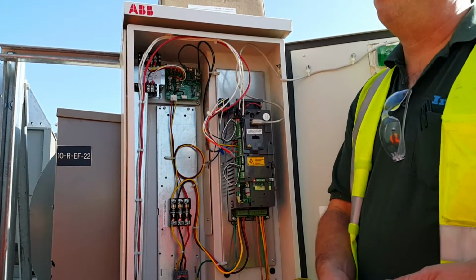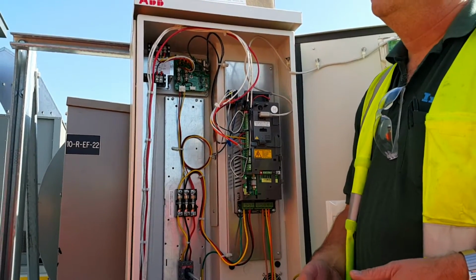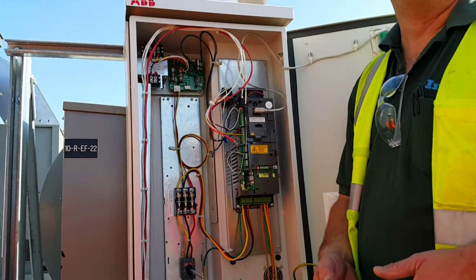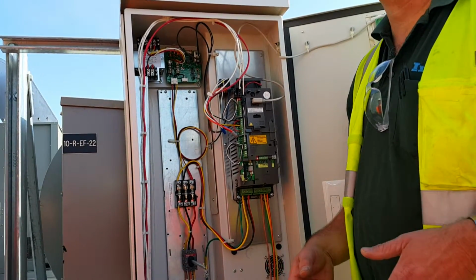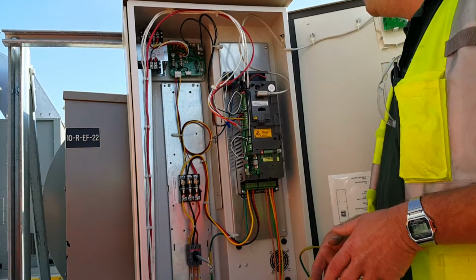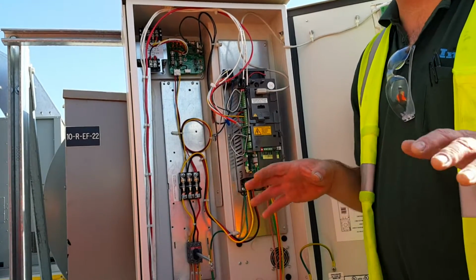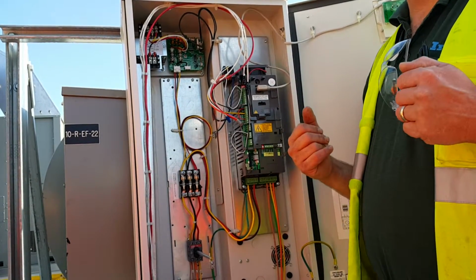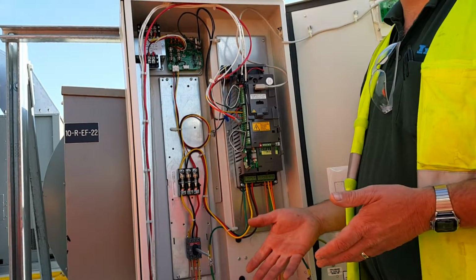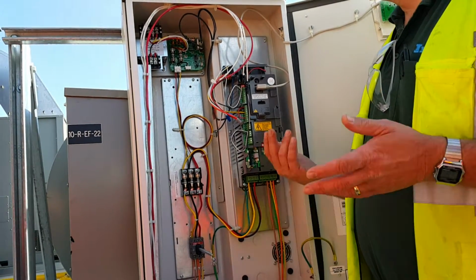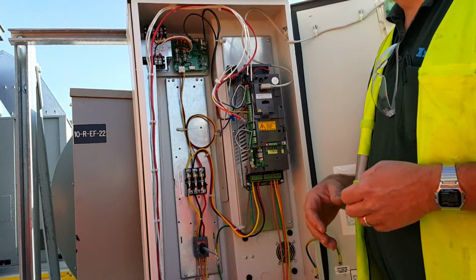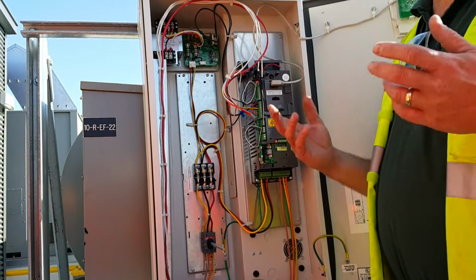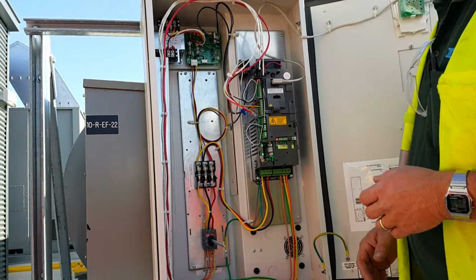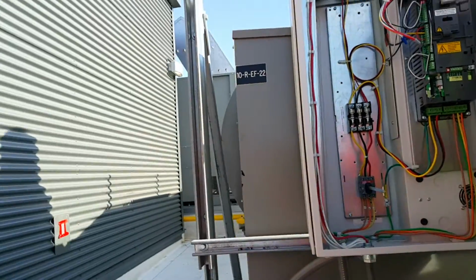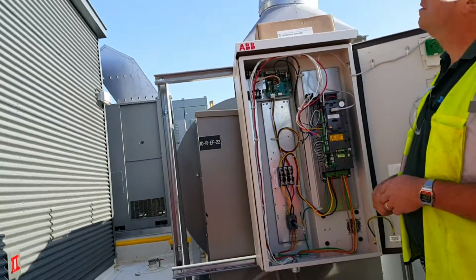Okay, we do have a bad motor. But nobody wants to change a motor if there's no problem with it. Then you really look foolish and you waste a bunch of time. But you also don't want to change the drive. I see that a lot, where drives get replaced, and there's nothing wrong with the drive. The whole time it's been the motor, and these aren't cheap. Little ones aren't so bad. As you get up to the bigger ones, it gets really expensive. So yeah. Oh boy.